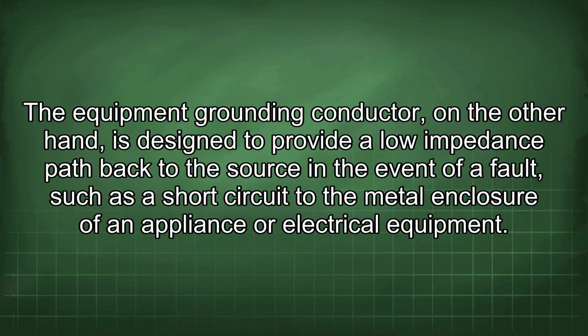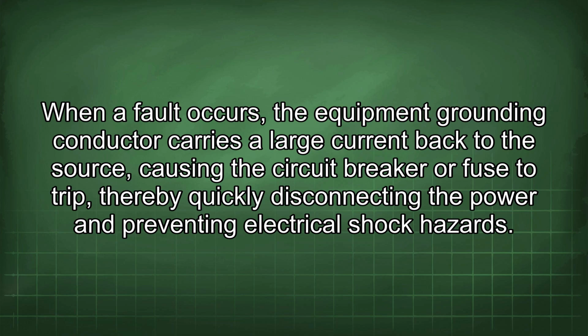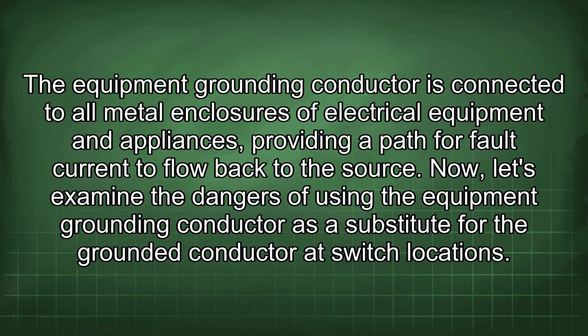The equipment grounding conductor, on the other hand, is designed to provide a low impedance path back to the source in the event of a fault, such as a short circuit to the metal enclosure of an appliance or electrical equipment. When a fault occurs, the equipment grounding conductor carries a large current back to the source, causing the circuit breaker or fuse to trip, thereby quickly disconnecting the power and preventing electrical shock hazards. The equipment grounding conductor is connected to all metal enclosures of electrical equipment and appliances, providing a path for fault current to flow back to the source.